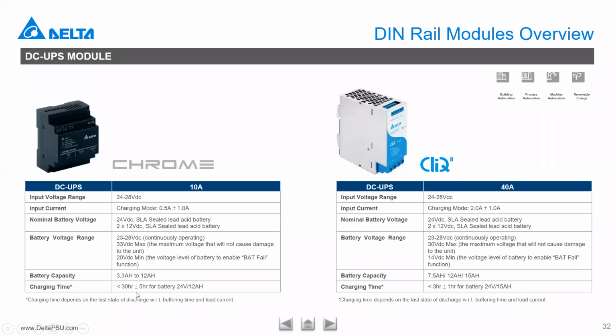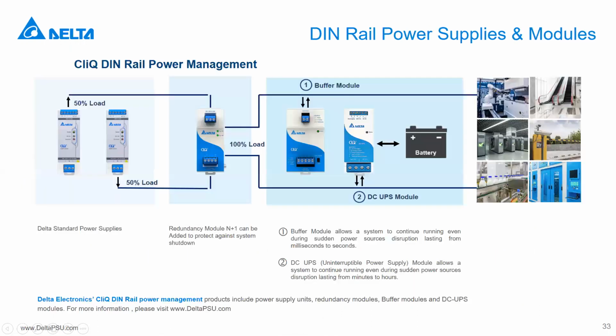So if we use the 12 amp hour battery, we are looking at slightly under 30 hours at 10 amps. If using 40 amps with a 15 amp hour battery, we are looking at slightly under 3 hours. So this is a typical connection for this UPS.